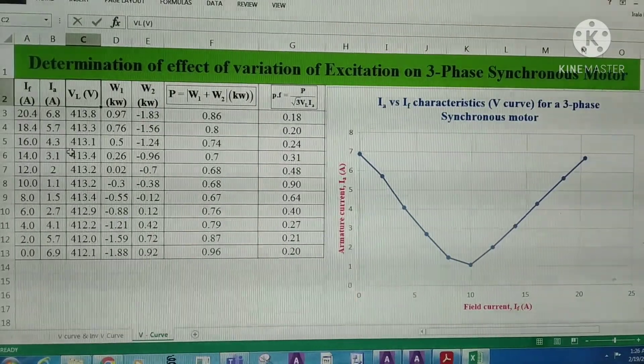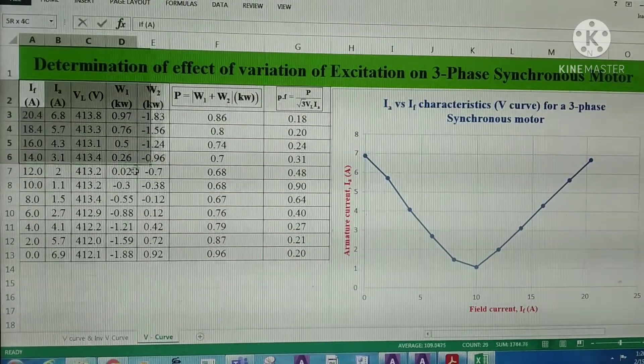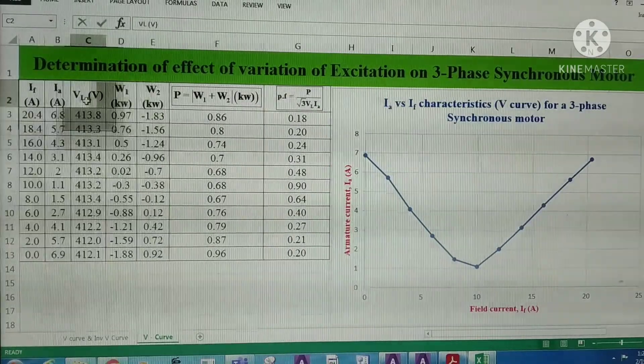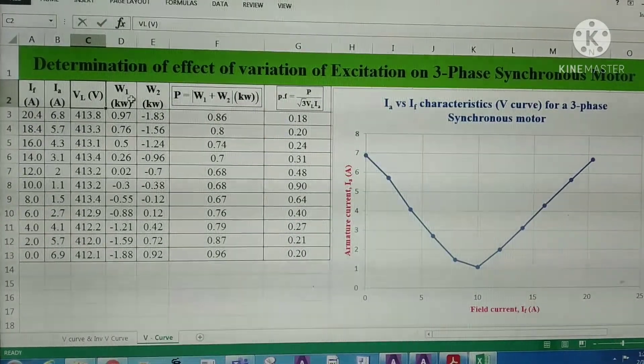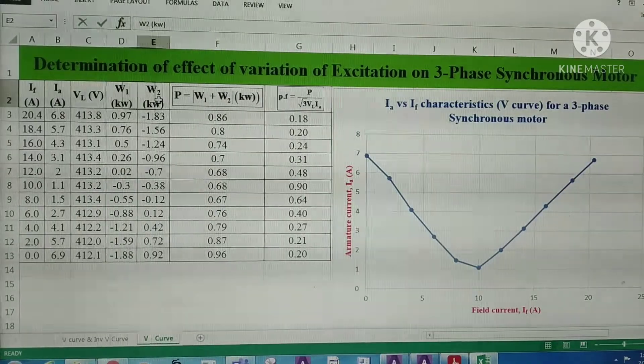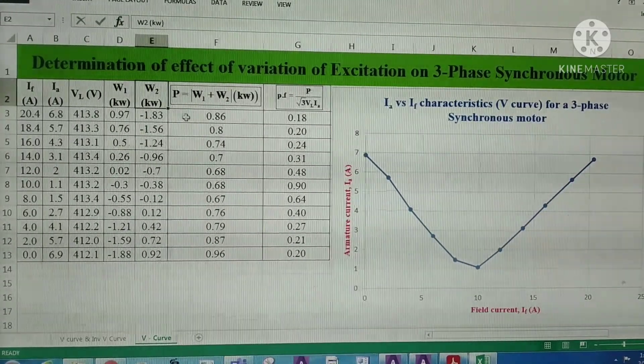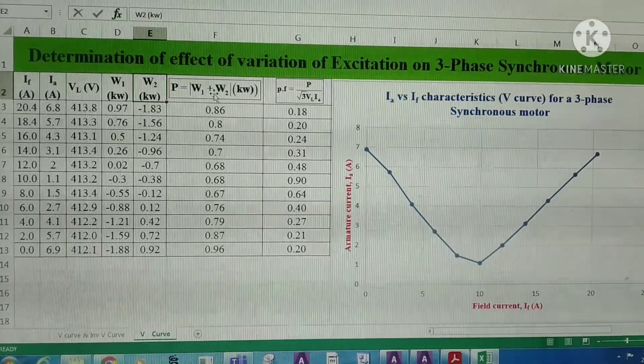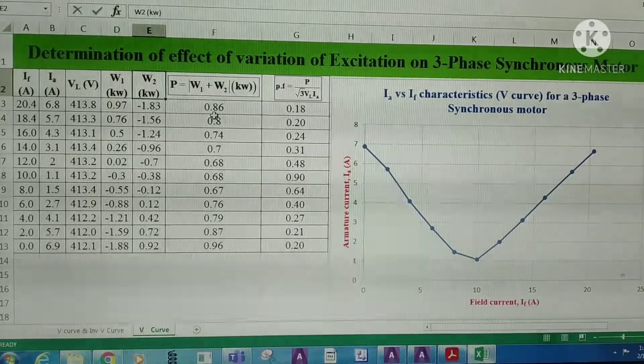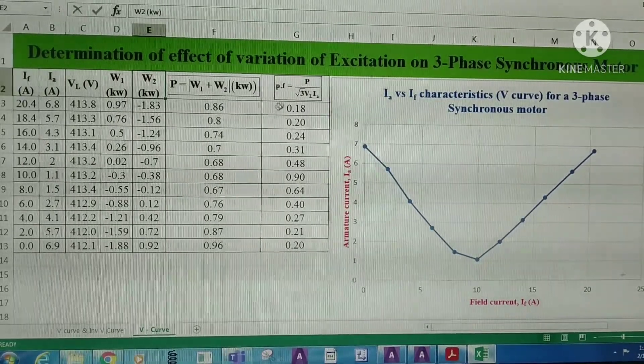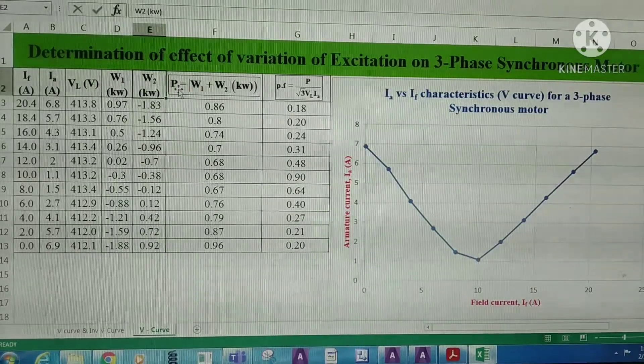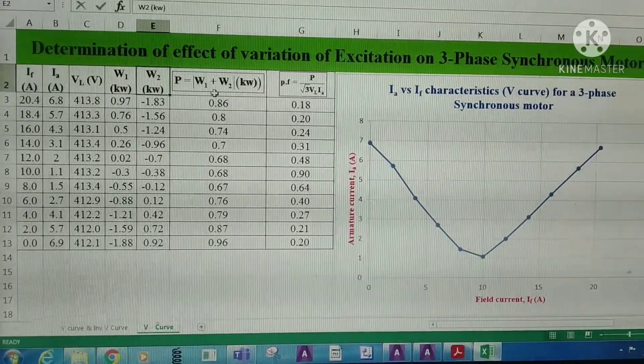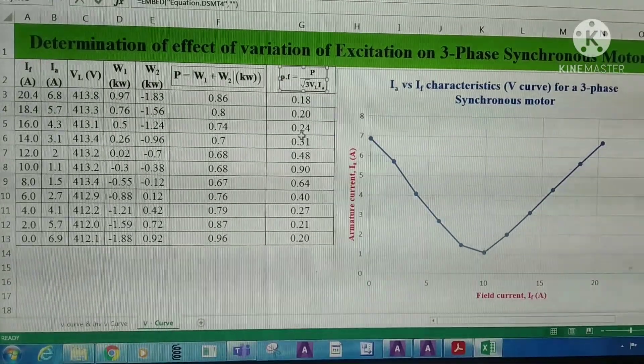From the experiment, we have noted down the experimental values — that is, field current, armature current, line voltage, W1 wattmeter reading, and W2 wattmeter reading. From W1 and W2, we have determined the total power consumed by the 3-phase synchronous motor. From the total power, line voltage, and current, we have determined the power factor.